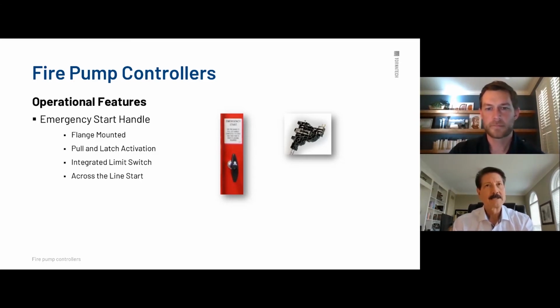One idea I want to add to this: on the emergency start handle, if you're doing commissioning, a lot of times this is overlooked, but sometimes the AHJ wants to test at least one, or sometimes even six. As Cole mentioned, you want to pull and twist clockwise and lock it, even though there's an electrical interlock there, because what you are actually doing is mechanically closing the contacts of that contactor physically. So there is a procedure that we suggest. It's in our manual. It's actually in a couple of the other manuals.